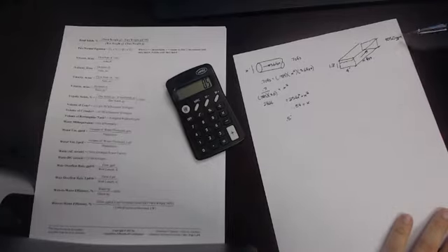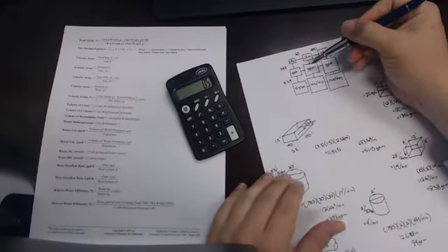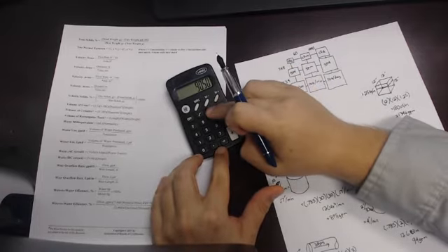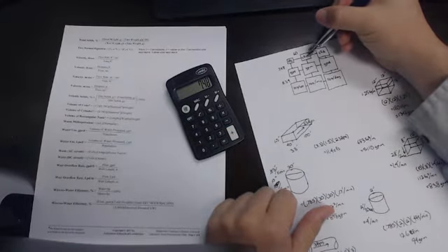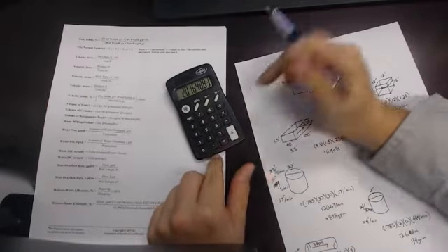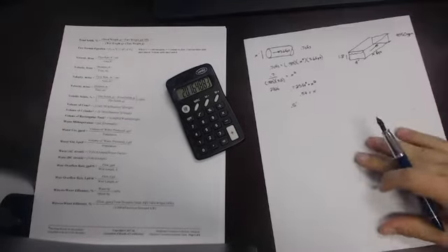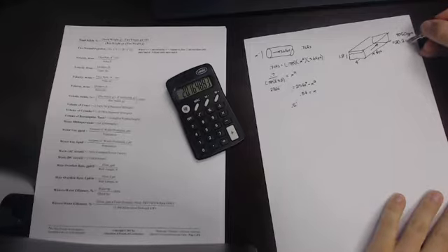Alright, so we've got to convert our gallons per minute to cubic foot per second. So we take 9,050 divided by 7.48, because we're going from a bigger box to a smaller box. We're going to seconds, so then we divide that by 60, and we get 20.2. We'll round up. 20.2 cubic foot per second.